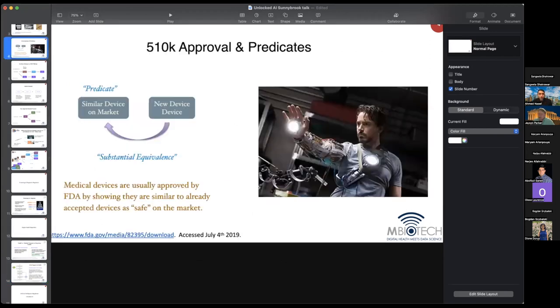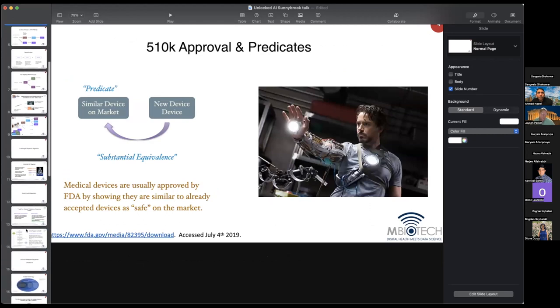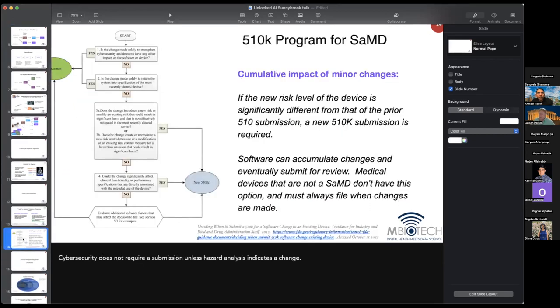Coming back to traditional medical devices — if you make a change to your device, you're going to submit a 510-K if you're 510-K approved to begin with. But when it comes to software, just because you change your software doesn't mean you need to submit a 510-K. The manufacturer is allowed to make the judgment call about when it is time to submit a 510-K.